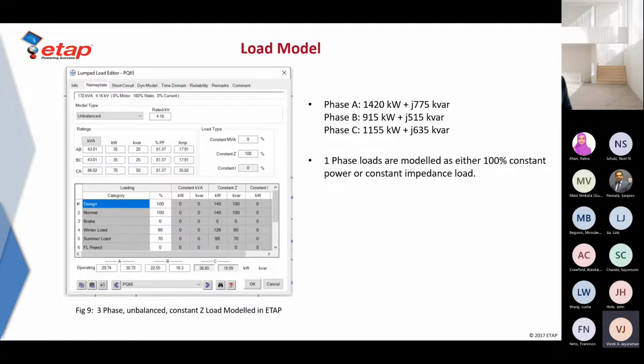One of the more difficult approaches was that currently ETAP does not have a way where you can model a single phase load with constant current. So they are modeled as constant impedance or constant power. And in this case, we have moved forward with modeling them as constant impedance load.